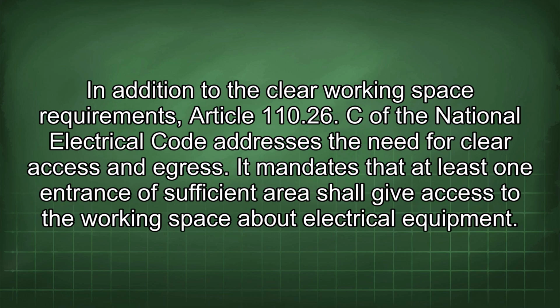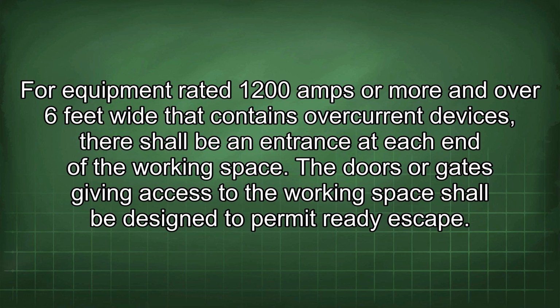In addition to the clear working space requirements, Article 110.26 C of the National Electrical Code addresses the need for clear access and egress. It mandates that at least one entrance of sufficient area shall give access to the working space about electrical equipment. For equipment rated 1200 amps or more and over 6 feet wide that contains overcurrent devices, there shall be an entrance at each end of the working space.